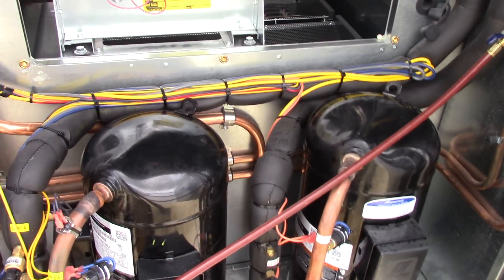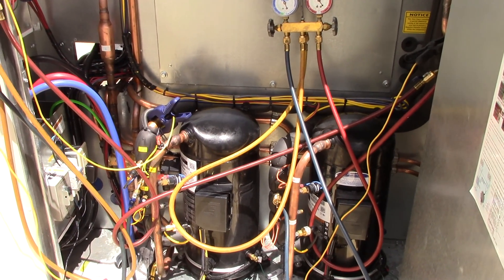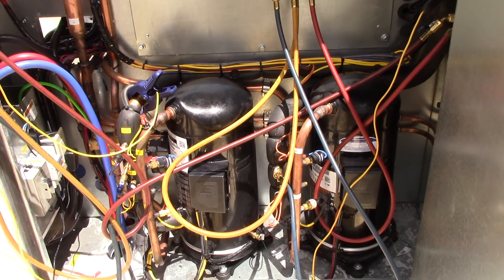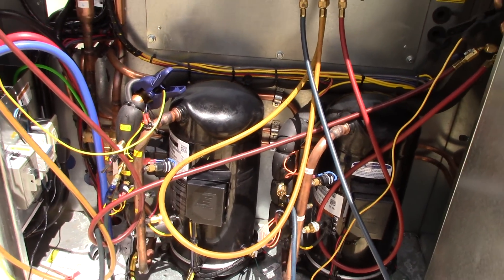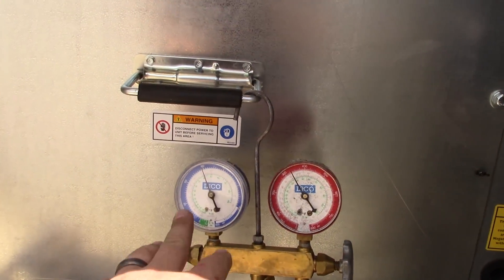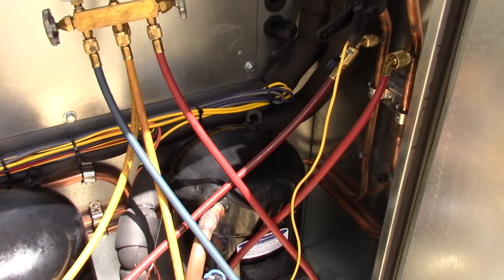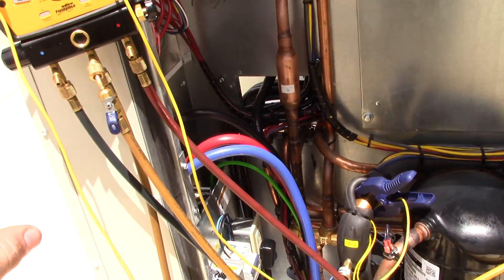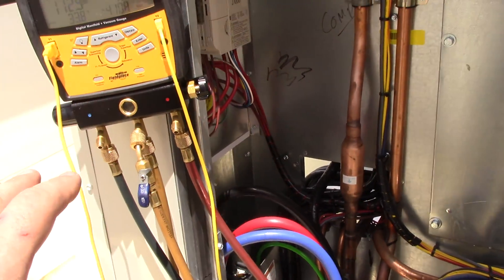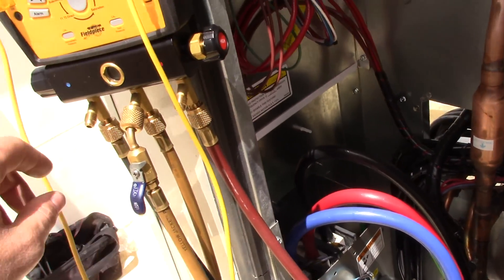We've got the unit up and running, but there are a lot of parameters that have to be gone through with the AAON install tech. Right now we're doing the test of the refrigerants. Looks like we've got about 52 degrees saturation temperature. Unfortunately, this is not my manifold — it's his, and he's got the high side connected to the suction side, which is backwards.